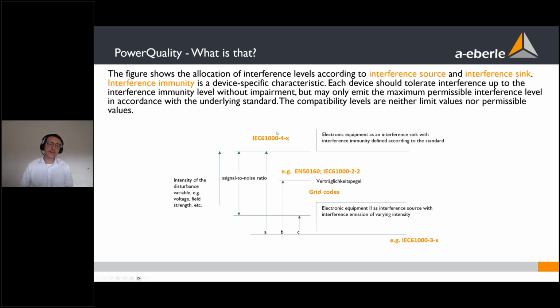And this is the IEC standardization, IEC 61000-4-X. And we, in the field of power quality, are in between, because we cannot even say if everything is stable, but someone has to control that. And this control mechanism is, for example, the EN 50160 standard, the product standard of voltage quality, not power quality. EN 50160 only has thresholds for the voltage, because it is the voltage that every device installed on the grid sees, and therefore it has to be controlled.